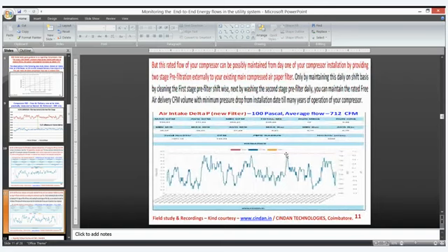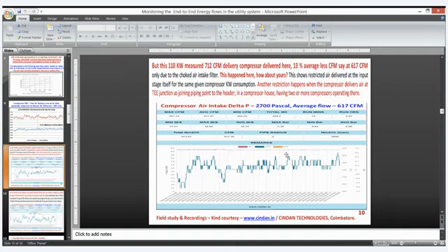At 100 pascals, it is 712 CFM. At 2700 pascals, with a choked filter, after 2 months it is around 617 CFM. This means we purchased the compressor to deliver around 0.17 kilowatt per CFM. It's the best branded compressor, but due to the choked inlet filter, it has dropped to 0.20. This is an appreciable loss, especially on the compressed air flow rate.